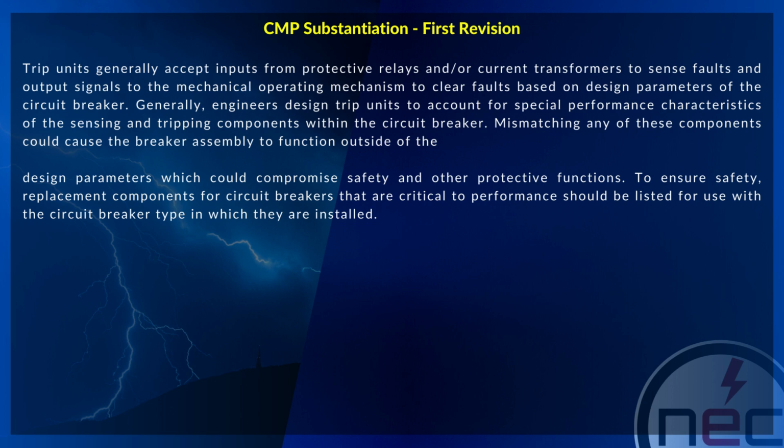To ensure safety, replacement components for circuit breakers that are critical to performance should be listed for use with a circuit breaker type in which they are installed.